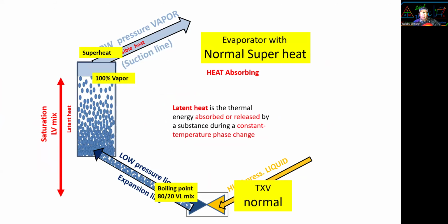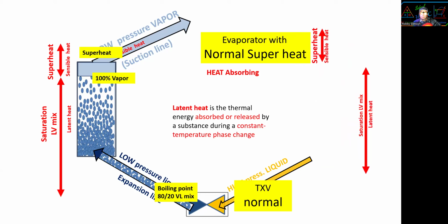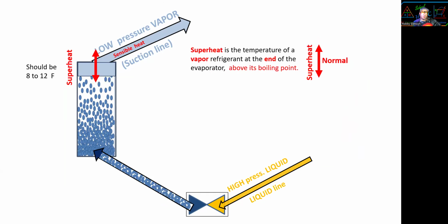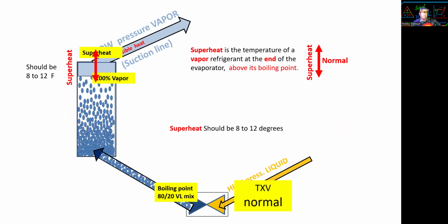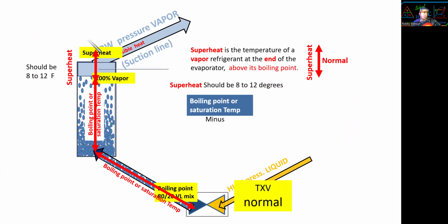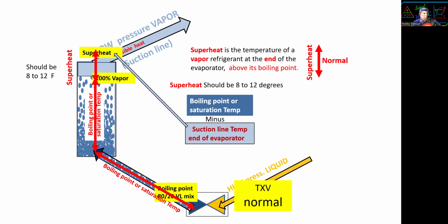Latent heat is the thermal energy absorbed or released by a substance during a constant temperature phase change. I covered that in basic. Superheat is your sensible heat, right? Sensible heat and your latent heat. Superheat is your sensible heat. The saturated liquid-vapor mix is your latent heat. And it's normal because we are at about 8 to 12. Same slide. Okay, so superheat should be 8 to 12.